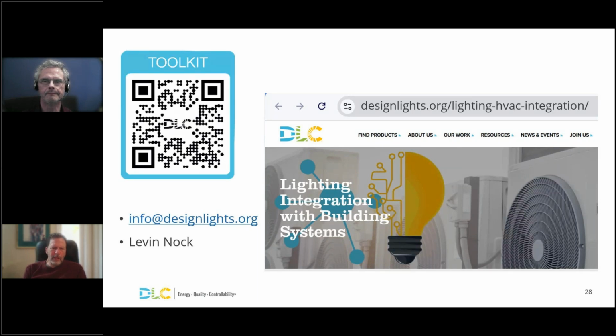And they elevated to this master system integrator that has to integrate everything, but not necessarily into the HVAC system, but into the building controls, operations, and building management system. So the master system integrator has to have a lot of fingers in a lot of different buckets. They need to know a lot about the different systems and how they communicate and how to do that integration. It's not super common in the industry yet, but it is becoming more prevalent as more Division 25 specifications are coming out.